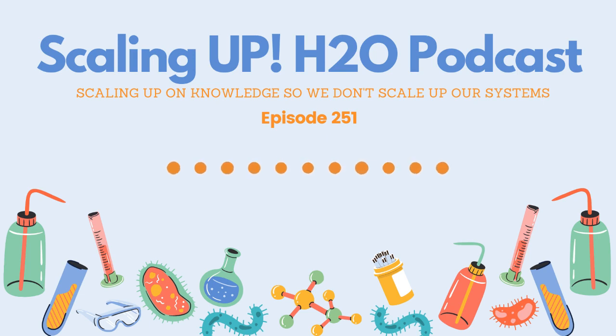Now, let's say the situation I just described is what you find. You find that either on a cooling tower or on a boiler, you have low conductivity. As I said before, why would you waste all your time doing all of your normal tests when you can suspect that all of those are going to be low? How do I know all the different things that you put into the boiler or the cooling tower are going to be low? Because your concentration levels are low, and that's reflected in your conductivity.